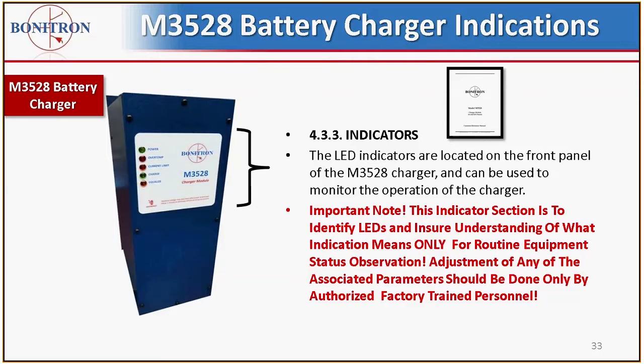For routine equipment status observation, adjustment of any of the associated parameters should be done only by authorized factory trained personnel. The reason for that is this is going to affect your charging current and battery equalization and things like that. So this training today is basic indicators and controls for ride-through school. There's much more involved to it. This is just for the casual observer or maintenance guy that's going to be monitoring the unit, to be able to have a little bit more information when he talks to the tech who may be trying to resolve a problem with the charger or the ride-through system.